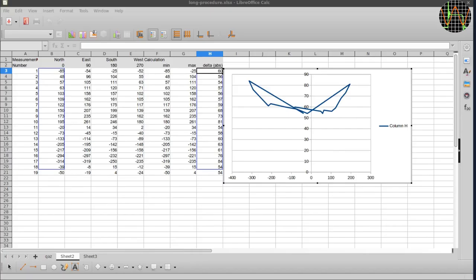If we plot the measurements using north for example against delta, we see this curve. It shows exactly what I described earlier. I started here and then adjusted VR4 until I found this steep rise on the right. Then I jumped back and started to adjust VR4 in the other direction finding the slope on the left, followed by the incredibly lucky jump back into the minimum. What I actually did is looking at the north values and seeing that a value of minus 40 to minus 10 should get me there. So all you need to do is power up the meter, insert your adjustment tool into VR4, turn the meter the right way up, orient it to north and tweak VR4 until you see the target north value.